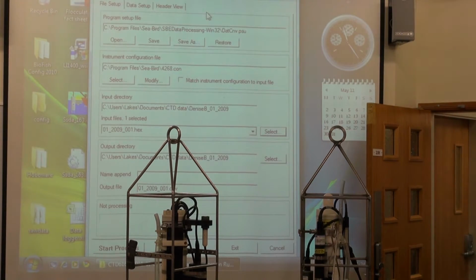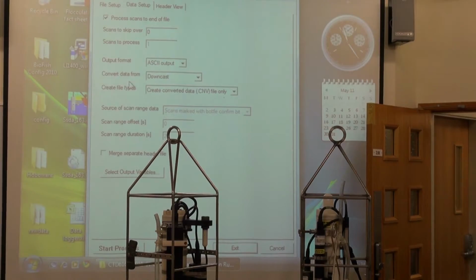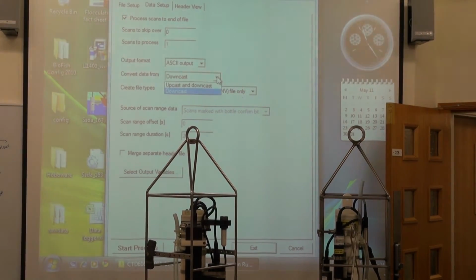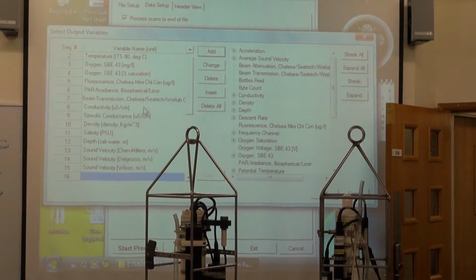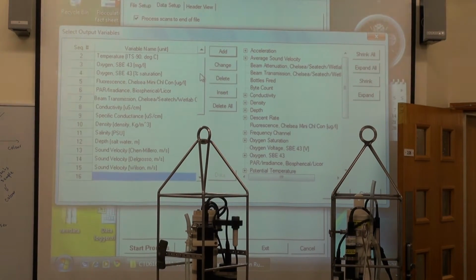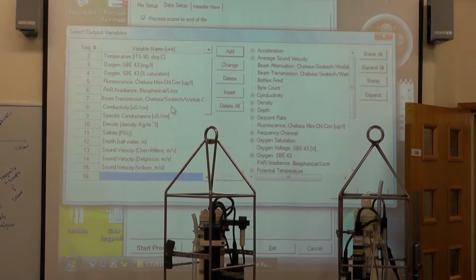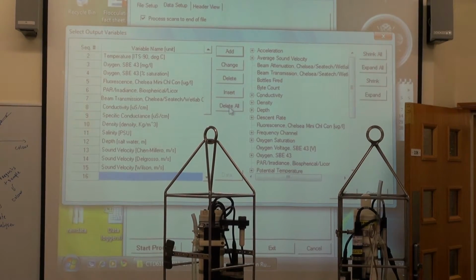Now, basically, it's usually set up good to go, but you can go into this data setup tab and select either to interpret just the downwards pass of the instrument or the up and down pass. We usually just do the downcast. And you can also chop and change around your output variables that you're going to interpret from the raw data. So for example, you've got separate depths for salt and fresh water, your oxygen in milligrams per litre and percent saturation, conductivity or specific conductance, whatever. I normally just do them all, but it's up to you. There's maybe some other possibilities you might be interested in here, things like sound velocity or whatever. So you can add, insert, delete, whatever you want, parameters that you can interpret.